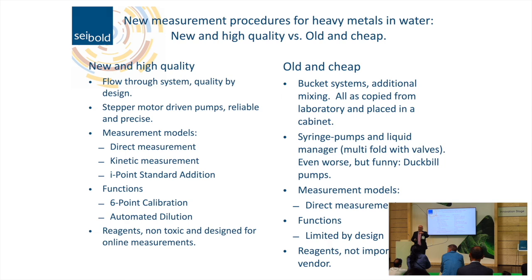The measurement models include direct measurements, kinetic I-point standard addition (where I-point stands for integral — measuring the area below the curve), and a six-point calibration for quality assurance. Our reagents are built by ourselves: non-toxic, non-hazardous, designed for the measurements, high resolution, and with a long shelf life. Other vendors do not pay enough attention to their reagents.